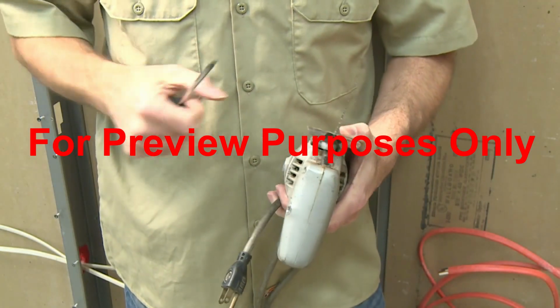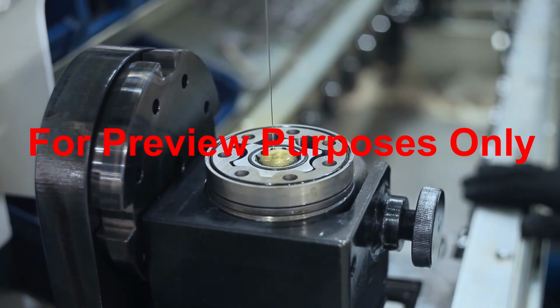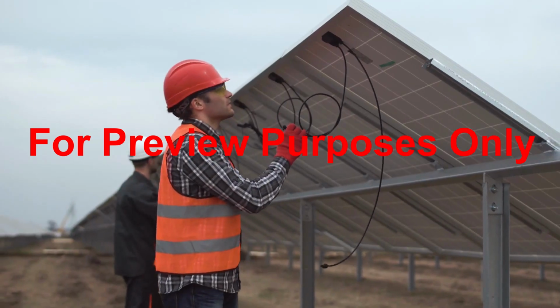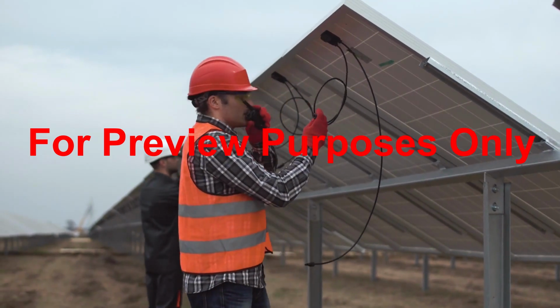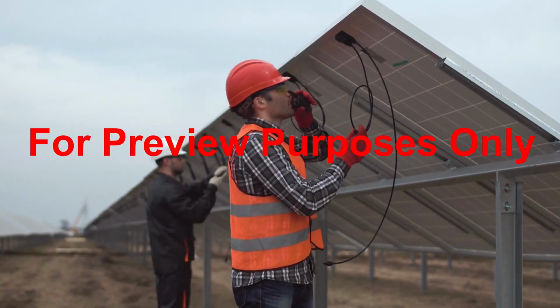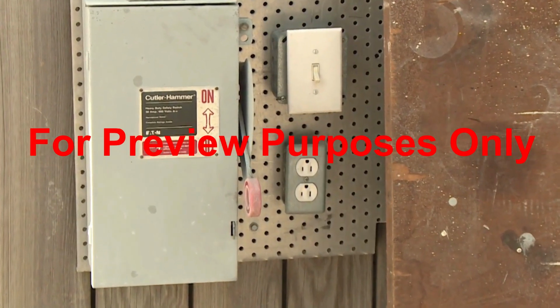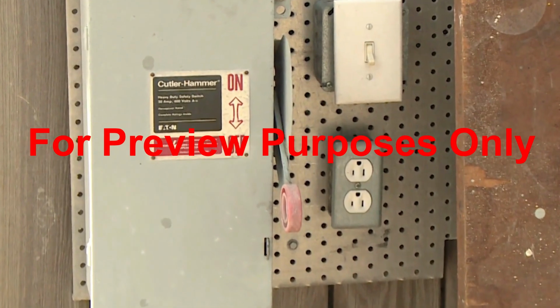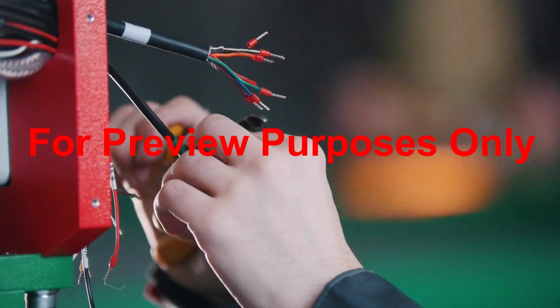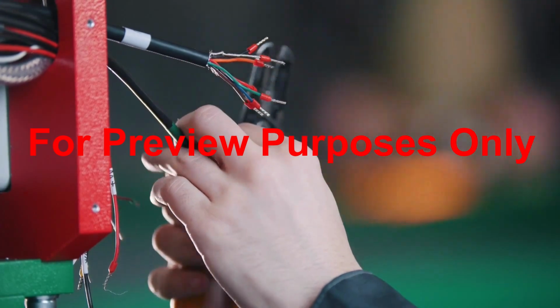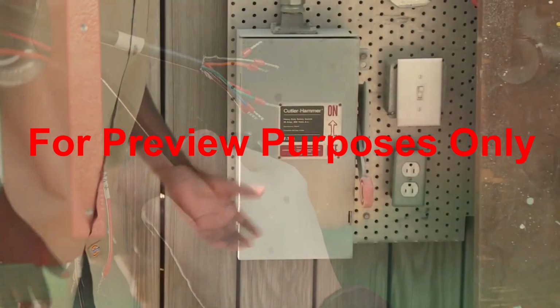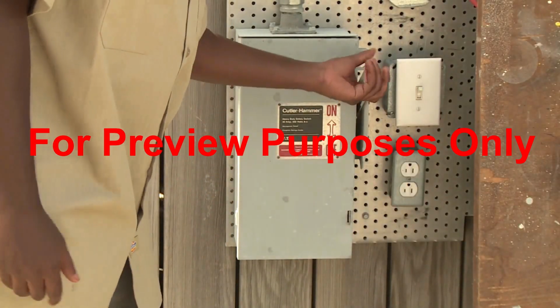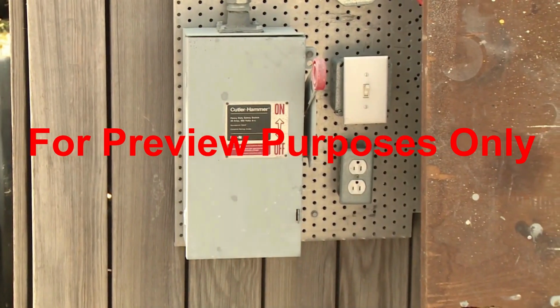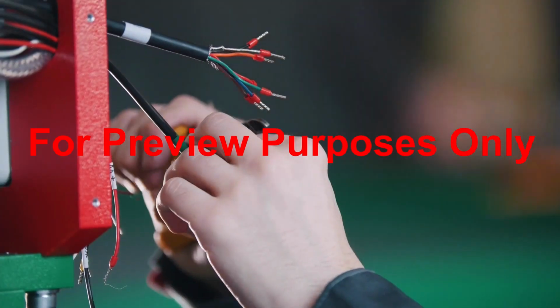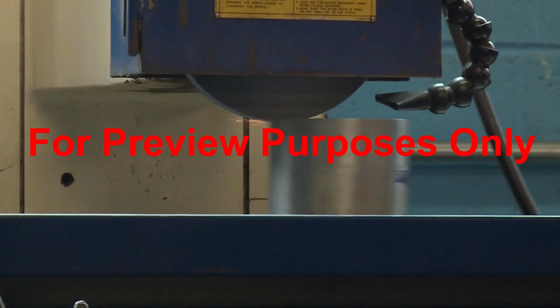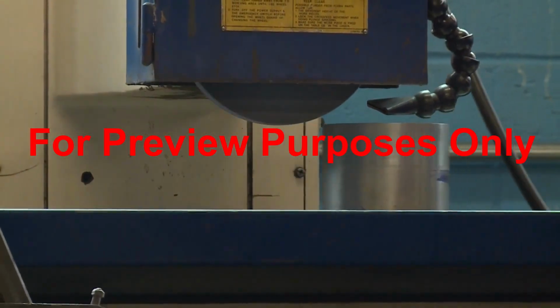Swapping out drill bits or saw blades, cleaning and lubricating moving parts, performing any of the maintenance or repair tasks that electrically powered equipment can require throughout the day. To accomplish any of these things safely, you first need to shut off the electricity that powers the equipment. And the electricity has to stay off while the work is being done. Switching the power back on could seriously injure, even kill the person servicing the machine, either because of the sudden flow of electrical current or the moving parts that it sets in motion.